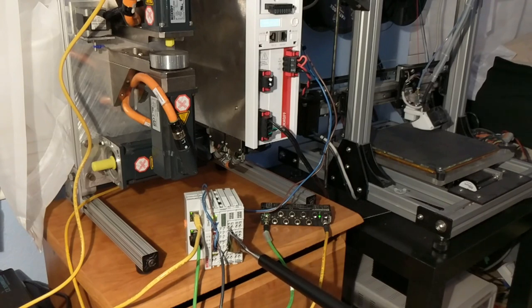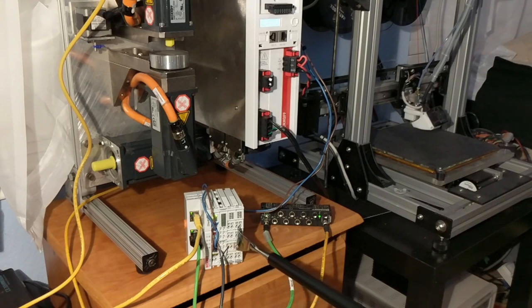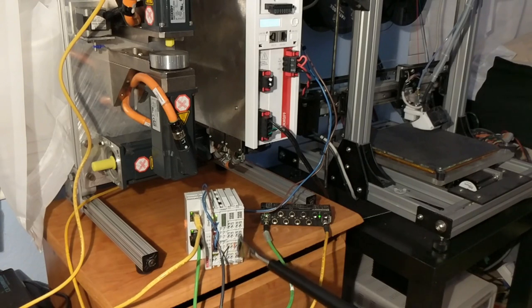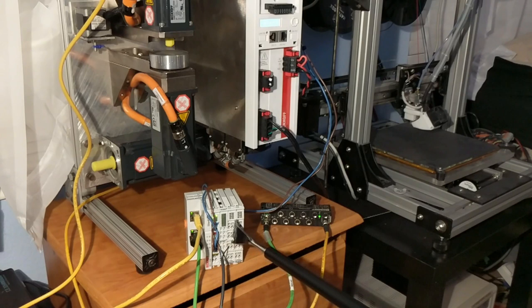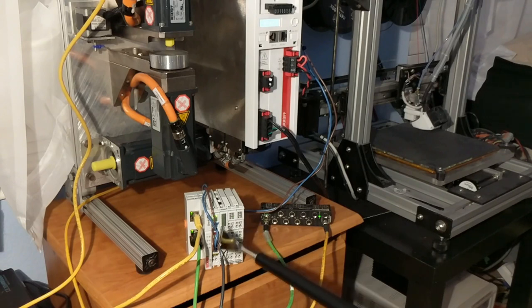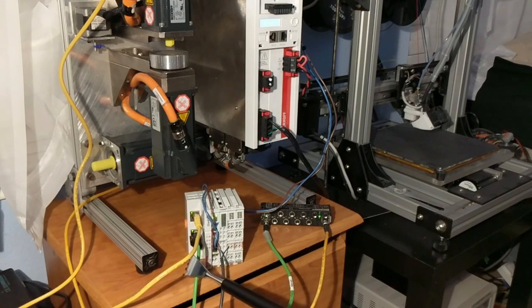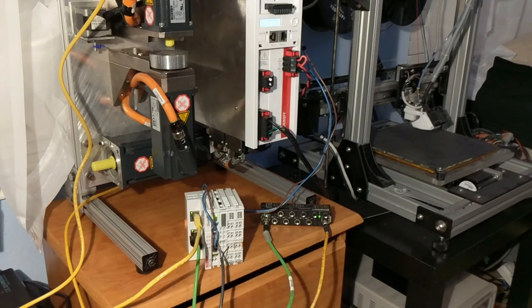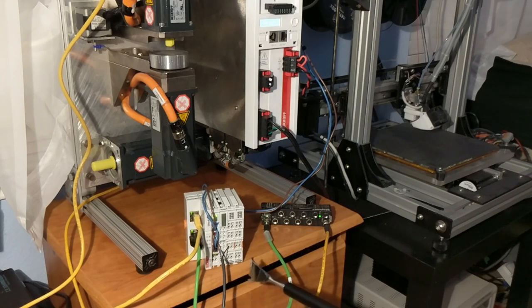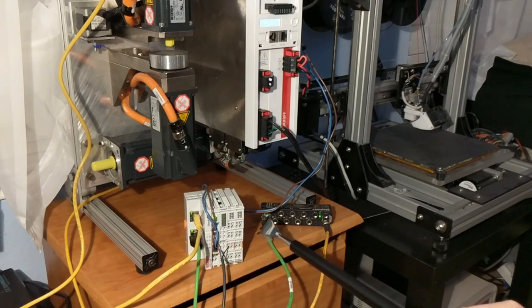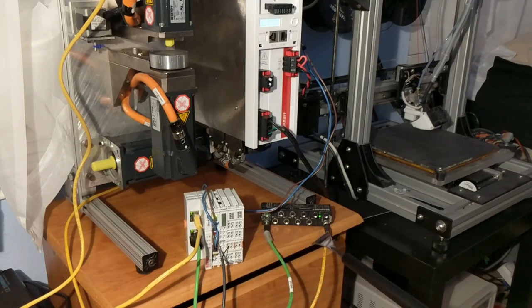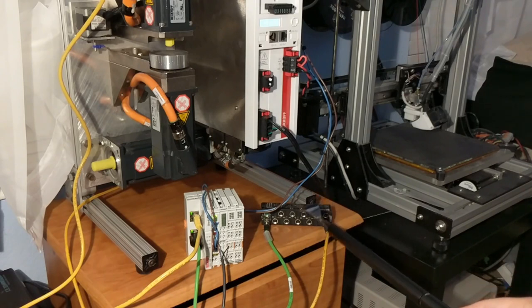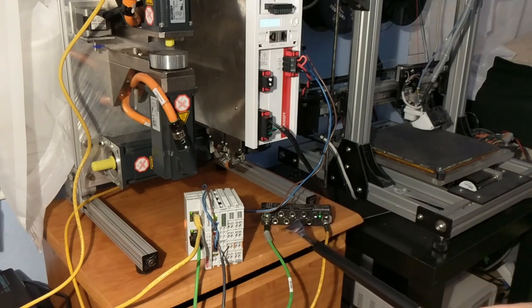That's digital input 24 volt DC, digital output 24 DC. So you could flip solenoids with this and read sensors with this. So that comes out at EtherCAT in this green cable here and it runs down to the floor back up here. And yellow is 24 volt power to this pod here that's an EP2318. It's got four digital inputs, four digital outputs.